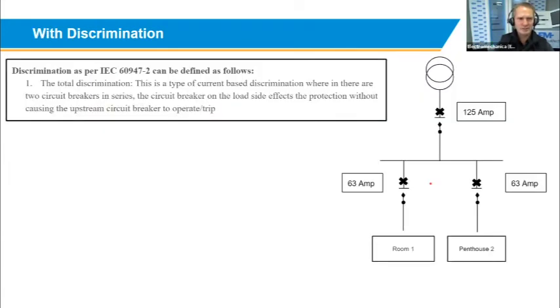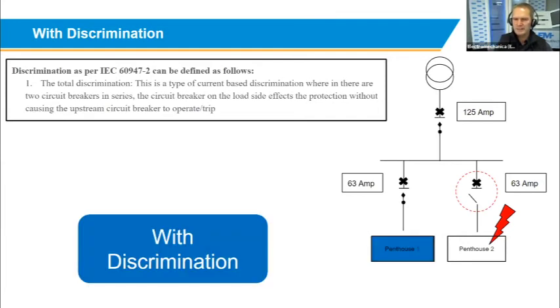According to the IEC standards, total discrimination is a type of current-based discrimination wherein there are 2 circuit breakers in series. The circuit breaker on the load side affects the protection without causing the upstream circuit breaker to trip. What they mean is that if something goes wrong and it's proper discrimination, the downstream breaker will open and only penthouse 2 will lose power. Your main supply to these 2 penthouses will stay on. So overcurrent occurs, the bimetal starts heating up, your breaker opens, and penthouse 1 carries on with normal life, and nothing interrupts their supply.